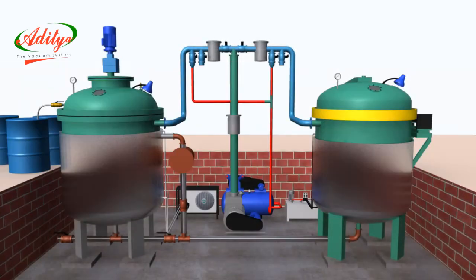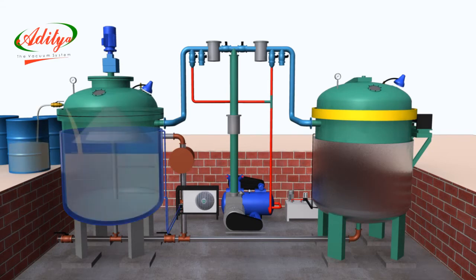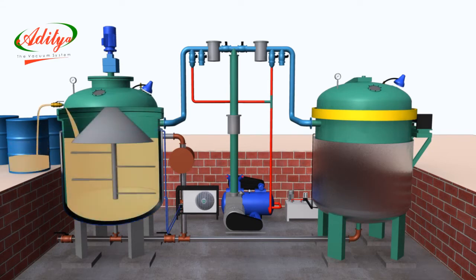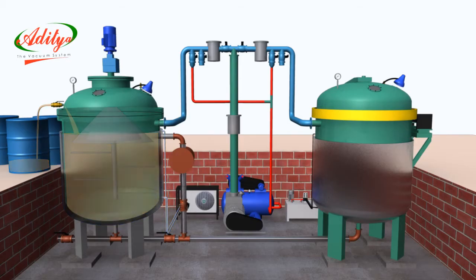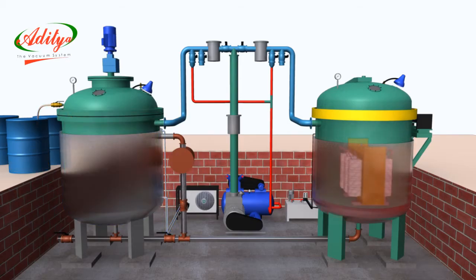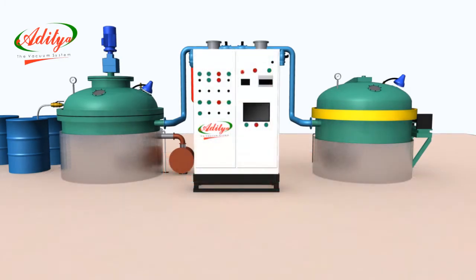Process of impregnation. Chiller and water pump are the independent units which will operate continuously for maintaining required temperature of resin or varnish inside the storage tank. The impregnating process commences with components preheating in drying oven or impregnating chamber. After sufficient drying in atmospheric pressure, components are kept in impregnating chamber for further drying under vacuum for suitable time. Let's demonstrate process of transformer impregnation as an example.